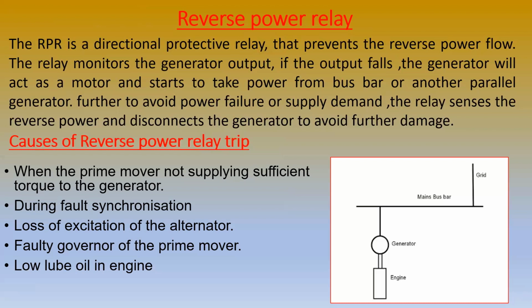Due to the low frequency, the generator cannot produce enough power to the bus bar, and that will also lead to the reverse power relay trip. So these are the causes of the reverse power relay trip. When the prime mover is not supplying sufficient torque to the generator, why can the prime mover not supply? That is because of low fuel, because of a faulty condition of the prime mover, or because of loss of excitation of the alternator. This may be the reason the reverse power relay trip has happened.